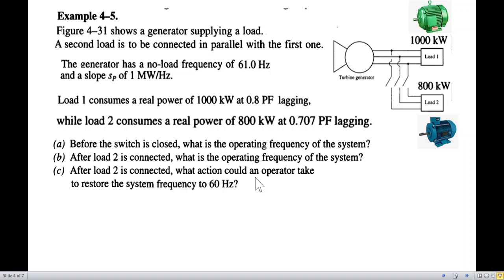Now, we have to find these three questions: before the switch is closed, what is the operating frequency of the system? After load two is connected, what is the operating frequency of the system? And after load two is connected, what action could the operator take to restore the system frequency? Let's recall that when we increase the load, what will happen? The generator speed will fall down. The shaft speed will fall down, and so will the frequency come down. And we have to have some mechanism to restore that frequency. By opening the throttle of the turbine, we can increase the speed, the power, and the frequency.